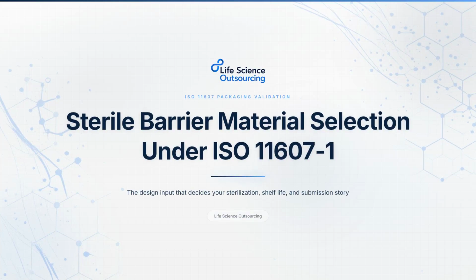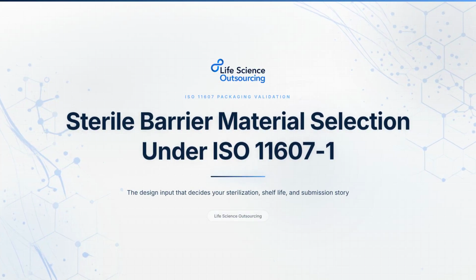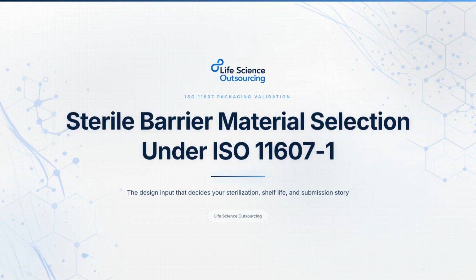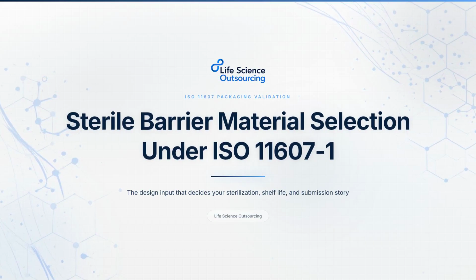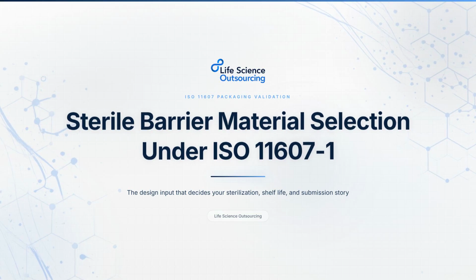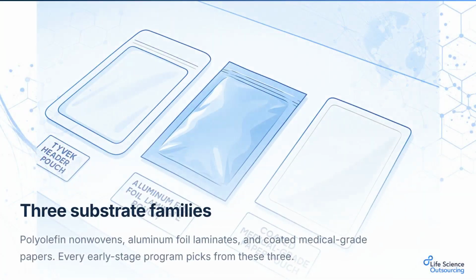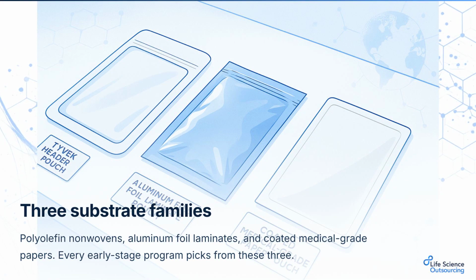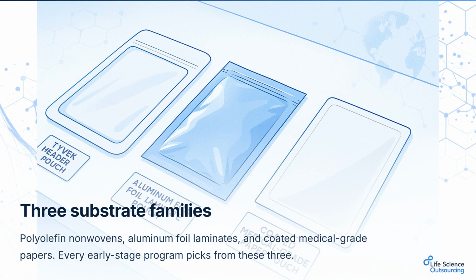Material selection is the decision that shapes everything downstream in packaging validation. Get it right early, and your seal qualification, aging study, and distribution simulation all build on a solid foundation. For a first sterile packaging configuration, you have 3 substrate families to choose from: polyolefin nonwovens like Tyvek, aluminum foil laminates, and coated medical-grade papers.